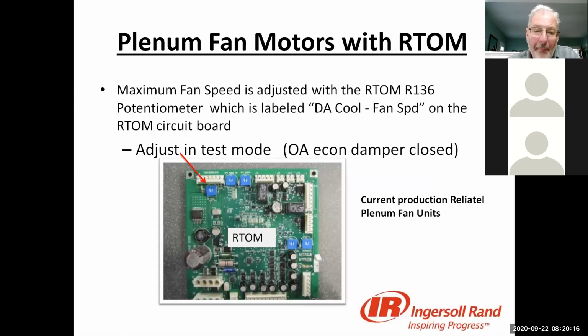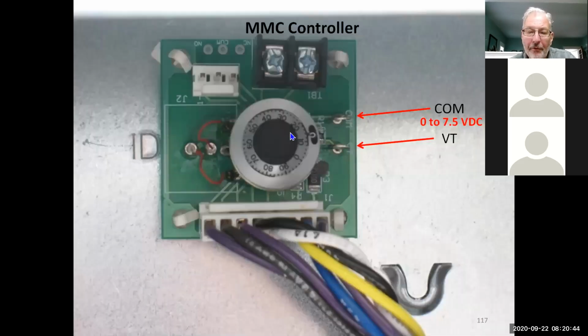So on the Reliatel models, it's a potentiometer on the options module. Okay, and that's where we're going to set the airflow. And when you get to set these, there's actually a pigtail that hangs out down below here. You put your voltmeter on there, set it to DC volts, and then you make your adjustments based on that voltage. And of course, on the old ones, the original ones, this just had a dial. You put your meter on here, you adjusted this from 5 to 7.5 volts DC, and you made your adjustments on this dial right here.